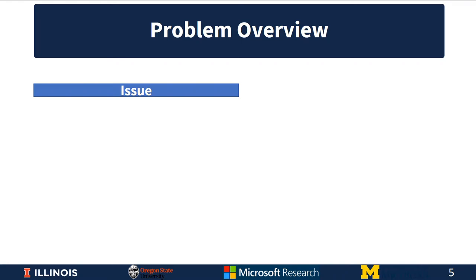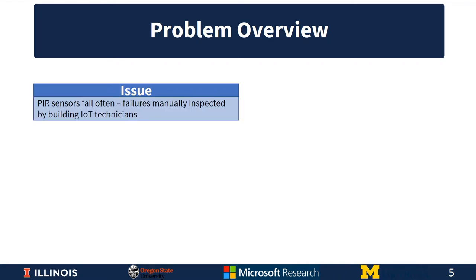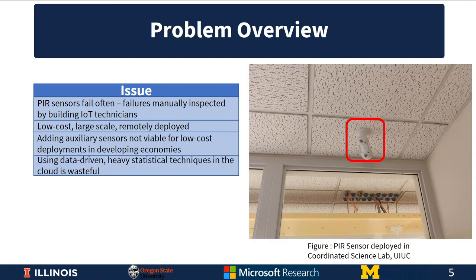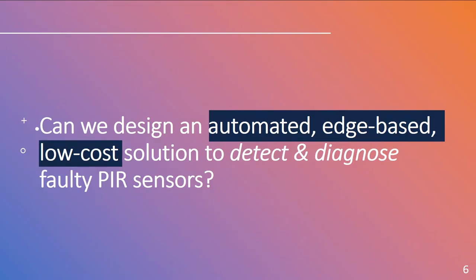The issue is that PIR sensors fail often, with failures being manually inspected by building IoT technicians. These sensors are low in cost, large in scale, and are remotely deployed, often at inaccessible locations in a building. Additionally, adding auxiliary sensors is not viable for low-cost deployments, particularly in developing countries. Lastly, using data-driven heavy statistical techniques in the cloud is wasteful of network bandwidth. So we ask: can we design an automated edge-based low-cost solution to detect and diagnose faulty PIR sensors?